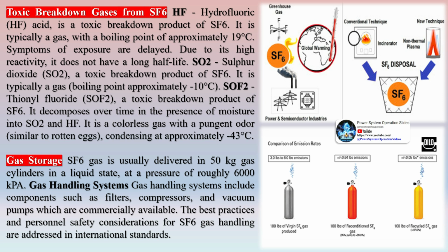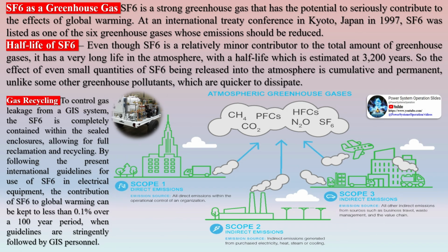SF6 gas is usually delivered in 50 kg gas cylinders in a liquid state, at a pressure of roughly 6,000 kilopascals. Gas handling systems include components such as filters, compressors, and vacuum pumps which are commercially available. The best practices and personnel safety considerations for SF6 gas handling are addressed in international standards. SF6 is a strong greenhouse gas that has the potential to seriously contribute to the effects of global warming. At an international treaty conference in Kyoto, Japan in 1997, SF6 was listed as one of the 6 greenhouse gases whose emissions should be reduced.